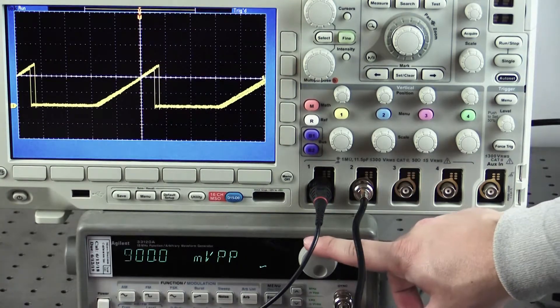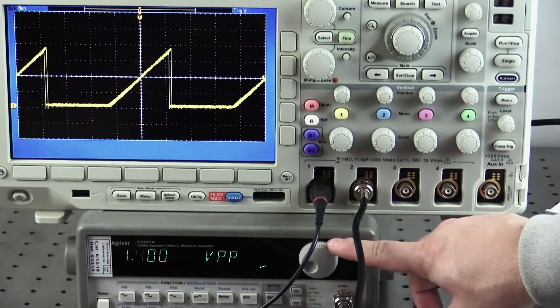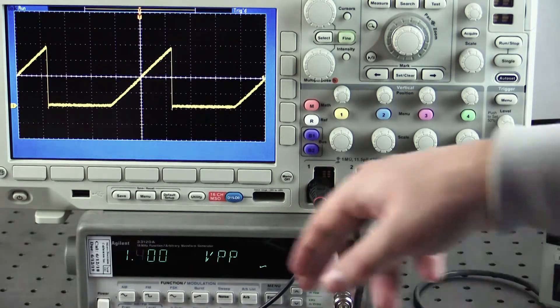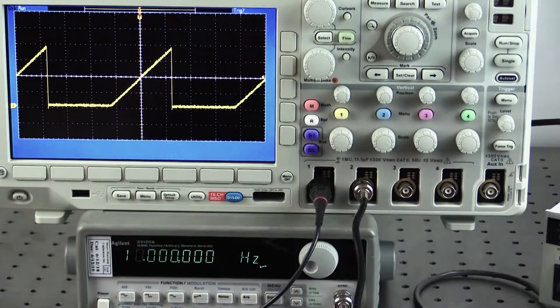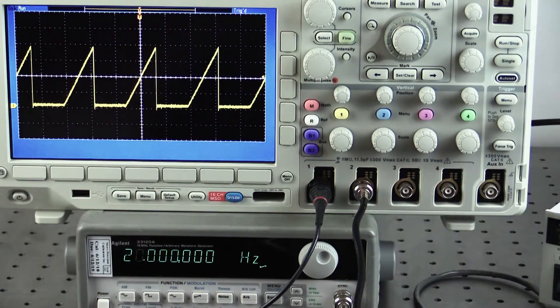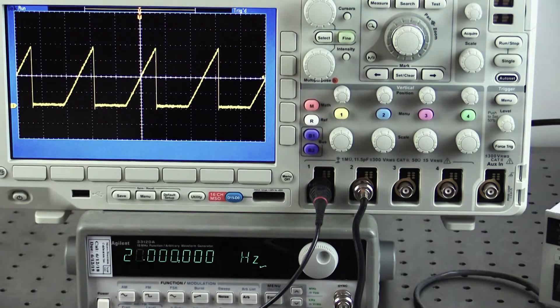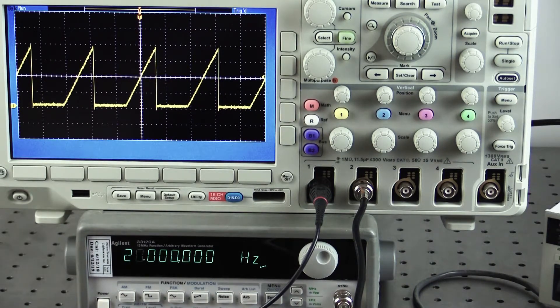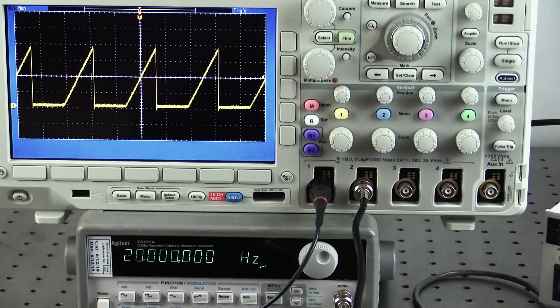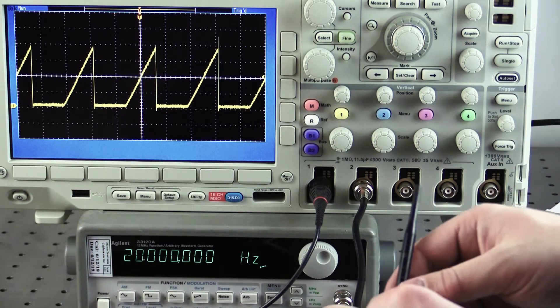The modulation transfer function in constant current mode is also 250 milliamps per volt. We set our function generator to produce a 1.4 volt peak-to-peak sawtooth signal at 20 hertz. This gives a maximum output current of 350 milliamps. Use an oscilloscope to monitor the laser diode output, again using LD Imon. The ILIM setting remains from the previous section. Enable the laser diode current.